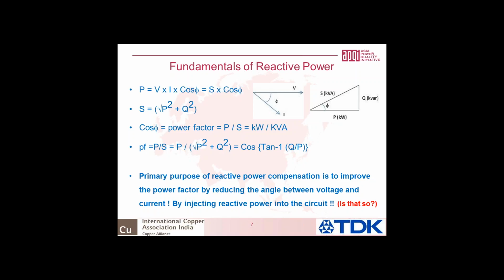And based on whichever mathematical equation you want, there are various equations for reactive power, for power factor. You can say cos phi is the ratio of real power to apparent power, which is kilowatt by kVA, or you can say it's P by root of P square plus Q square, or cos of tan inverse of Q by P. I mean, these are just the same mathematical equations. But the key today is, what is the primary purpose of reactive power compensation? All these days when people were working on a true balanced, true sinusoidal power network, the primary purpose of reactive power compensation was to improve the power factor by reducing the phase angle between the voltage and current by injecting a reactive power into the circuit.